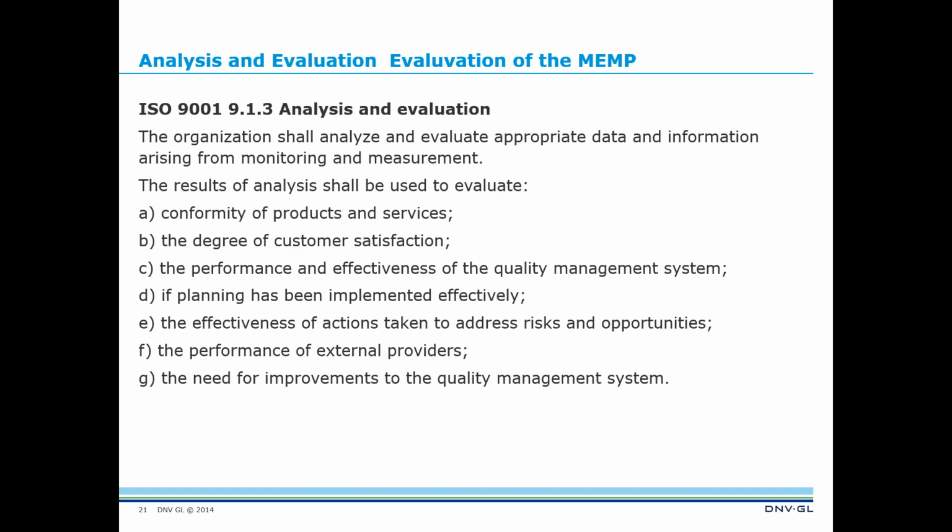But to do even that, I try to do it every 3 months. For example, if you have your business plan written down, then they want to see that it's effective. So everybody should have a business plan, which is the MEMP of the biomed shop. That's our business plan on how we run our operations from the time that our techs get there to what our process is if we have a SMDA violation or just a piece of equipment that failed during surgery or something. What do we do? How do we measure it?